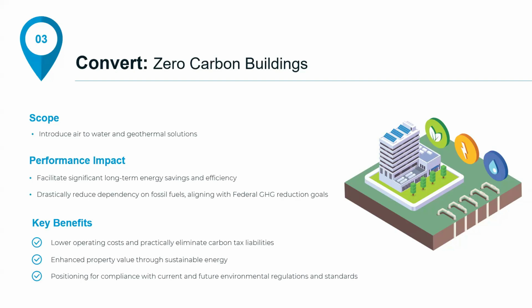This is the third step, and there's a fundamental reason for that. If you size your new heat pump system, whether air or ground source, off of the building's operation today, before you've optimized and conserved, you're going to invest too much capital, because you'll have to size it for the building loads we see today. You'd have to do that from a liability standpoint if nothing else.